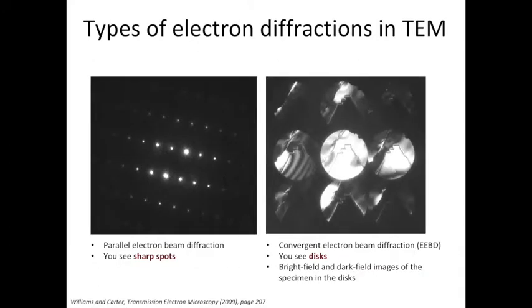When acquiring electron diffraction patterns, depending on how converged the beam is, you can either take the parallel electron beam diffraction or the convergent electron beam diffraction. From the examples shown here, you can see a typical example of the parallel electron beam diffraction on the left showing sharp spots. If you converge the electron beam when acquiring the electron diffraction pattern, you will get discs. This is called the convergent electron beam diffraction or CBED.